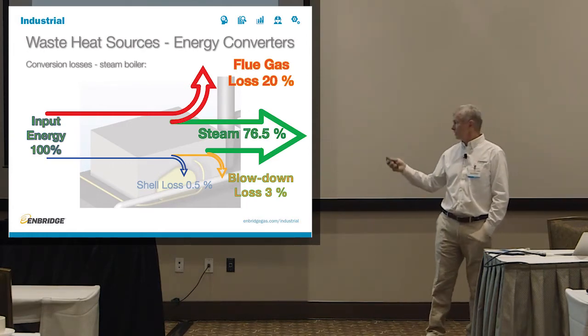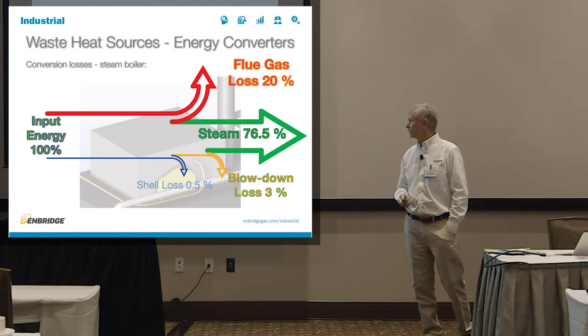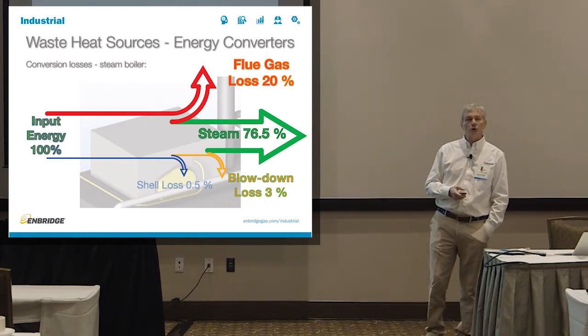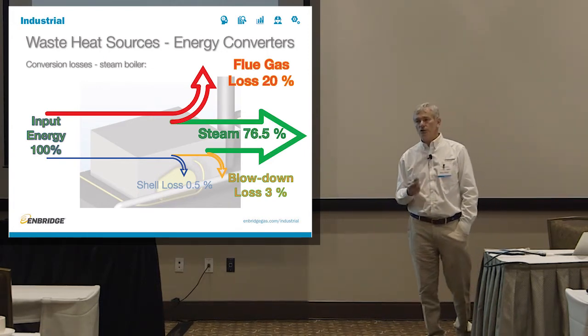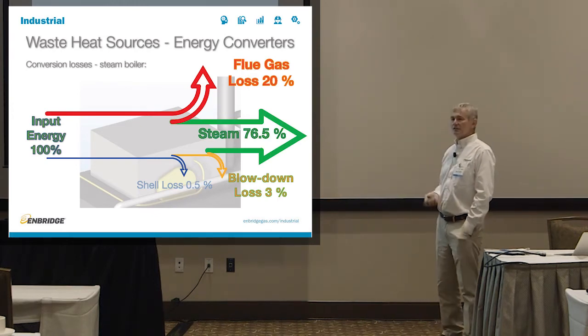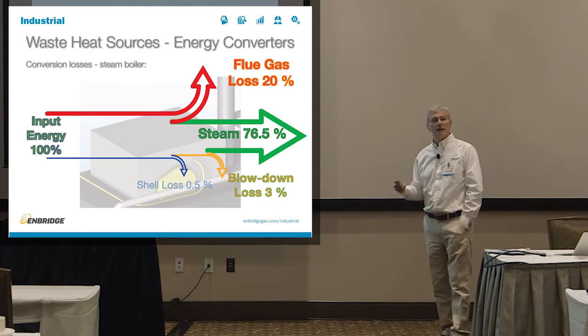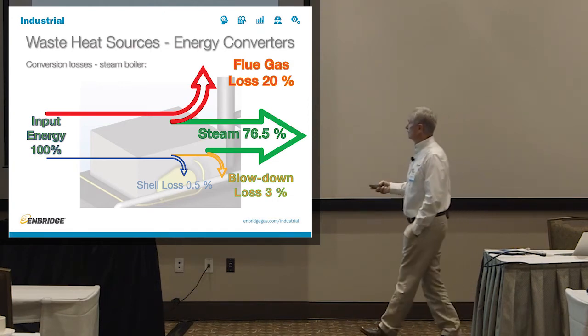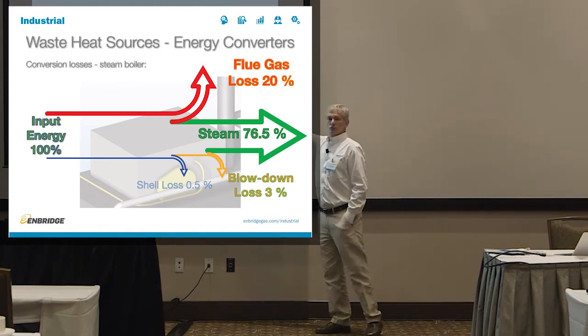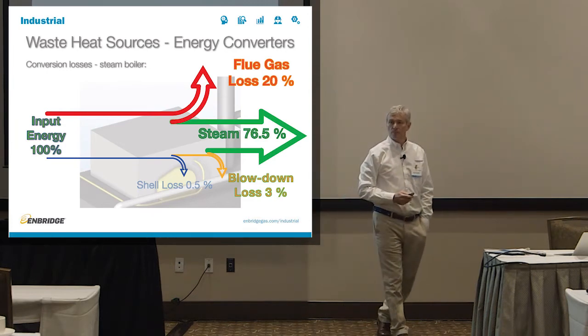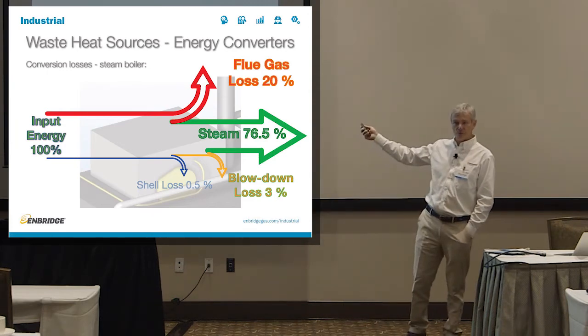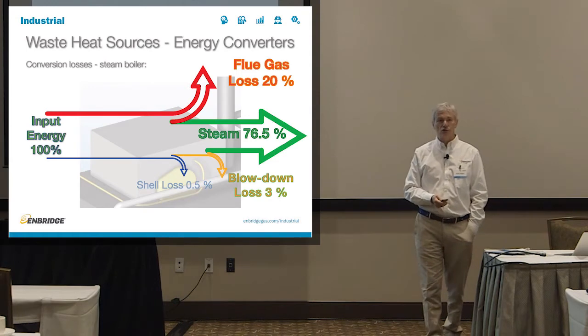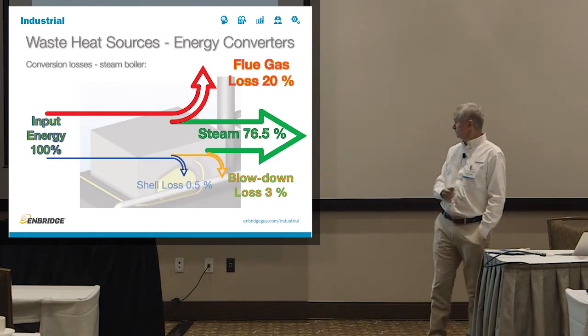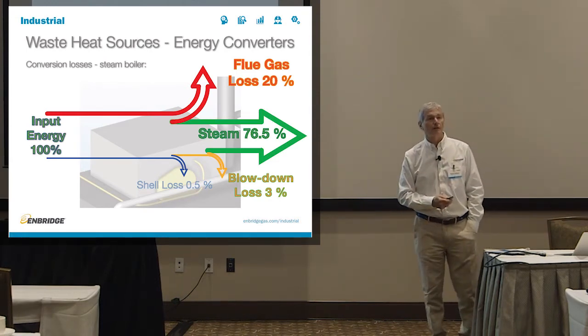0.5% goes into your shell losses, 3% usually on the blowdown, 20% goes up the flue. So essentially, you're throwing 20% of the energy up the flue stack. And you get 76.5% roughly in your steam. And this is really what you have. This is what you want. And considering you have a fixed requirement for that steam, you have to put in input energy that's 23.5% higher in value.